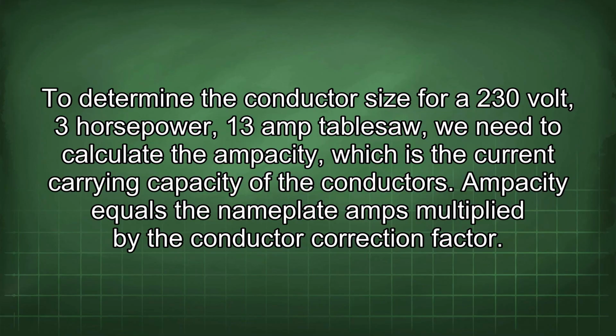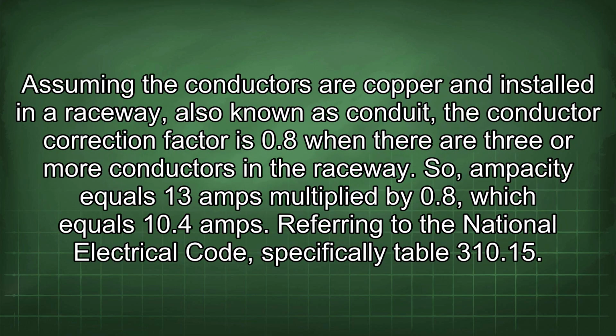To determine the conductor size for a 230 volt, 3 horsepower, 13 amp table saw, we need to calculate the ampacity, which is the current carrying capacity of the conductors. Ampacity equals the nameplate amps multiplied by the conductor correction factor. Assuming the conductors are copper and installed in a raceway, also known as conduits, the conductor correction factor is 0.8 when there are 3 or more conductors in the raceway. So, ampacity equals 13 amps multiplied by 0.8, which equals 10.4 amps.